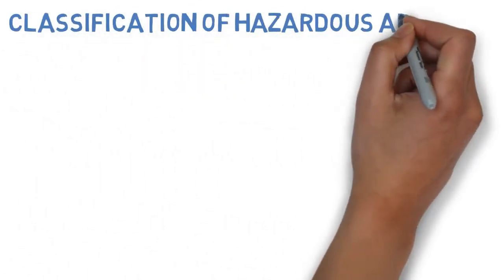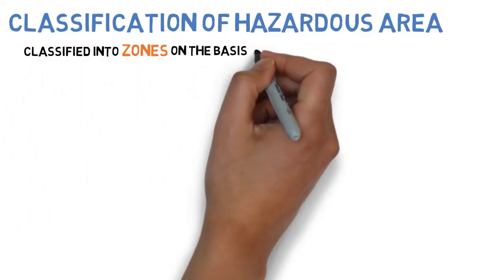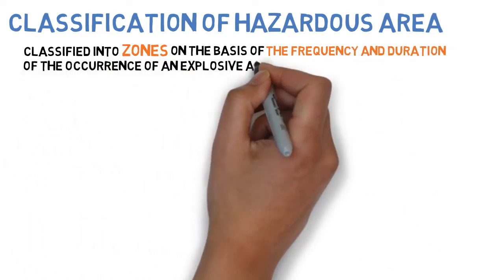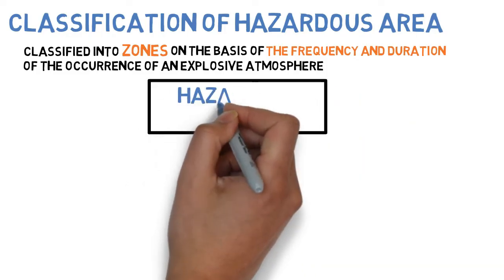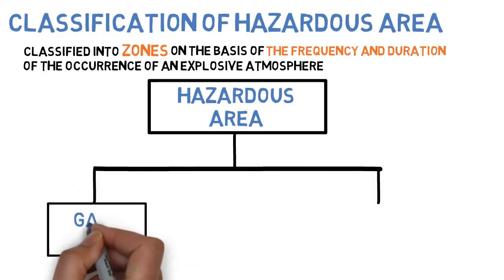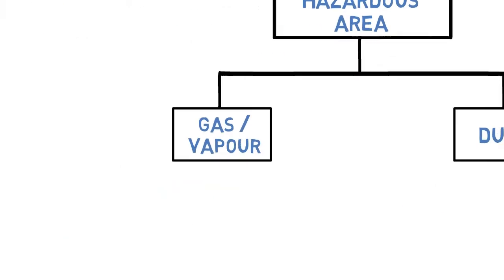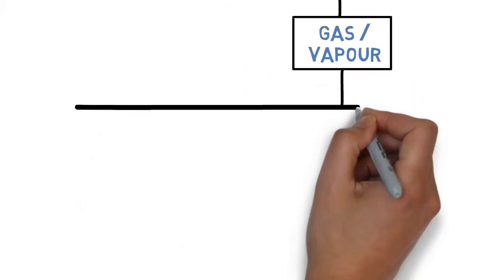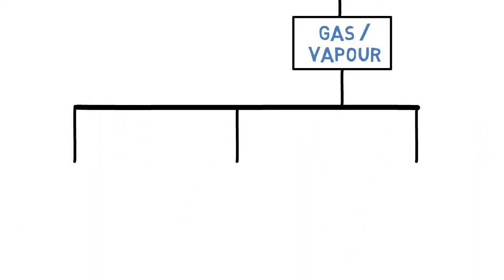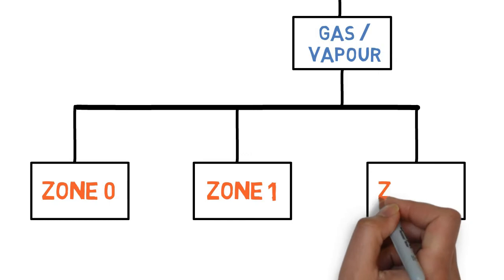Classification of Hazardous Area. Hazardous areas are classified in terms of zones, on the basis of the frequency and duration of the occurrence of an explosive atmosphere. Hazardous areas are classified into two major categories: gases or vapors, and dusts. Under gases or vapors, hazardous areas are classified into three different zones: Zone 0, Zone 1, and Zone 2.